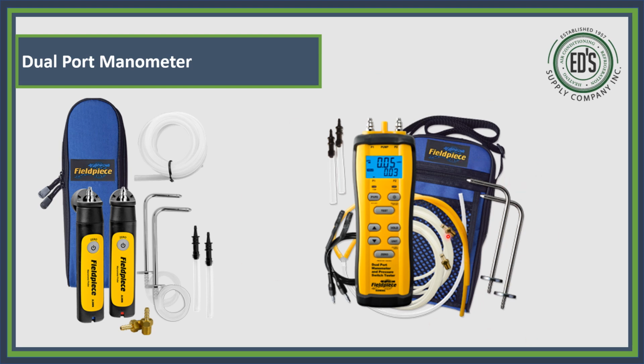And you'll see these here. This is for checking your gas pressure and your gas valve with these yellow hoses. What we're going to use is that white hose, and we're going to use these duct ports here. You cannot test your static pressure properly in ductwork without this, okay? This here is for your gas pressure. This part is for your ductwork.